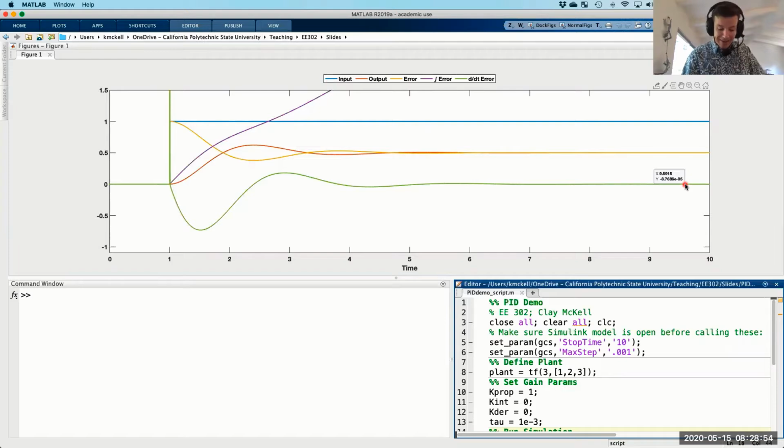Again, we are not acting on green or purple because we've set those gains to 0. We are currently only acting on yellow. I don't think we have quarter amplitude decay here. I can hardly see the second peak of the output. We've got steady state error, but we're not supposed to worry about that until step 2. So I am going to commence with my Ziegler-Nichols.